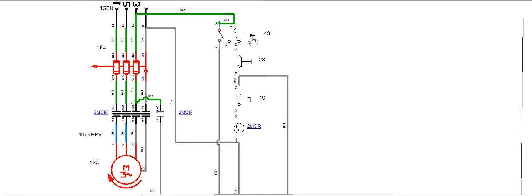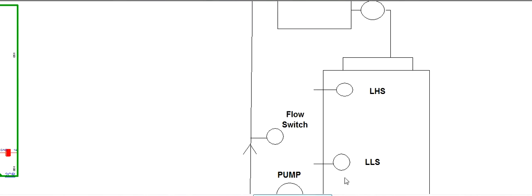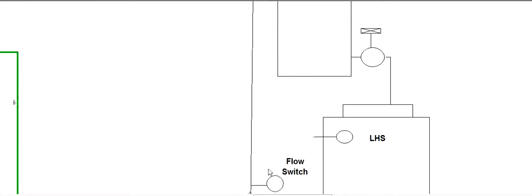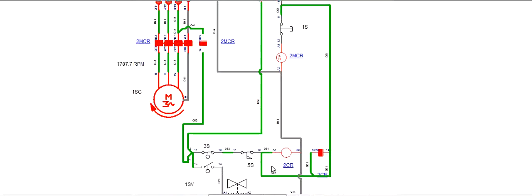I stop the motor and now I want to put it on auto mode. Switch to auto mode — it is now on auto mode, you can see. Power is going through to the low level switch. The water is low, so the low level switch activates and now the pump is running, pumping water to the top tank. You can see the flow switch is OK — there is a flow.